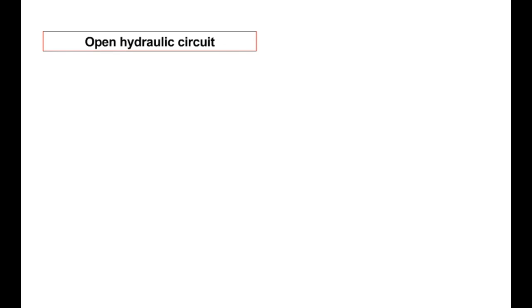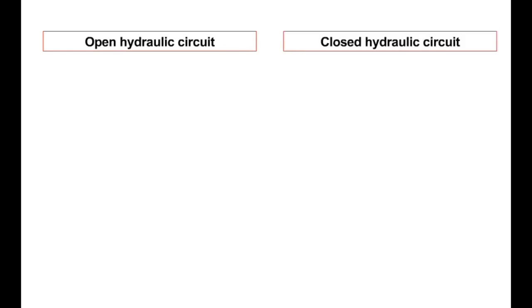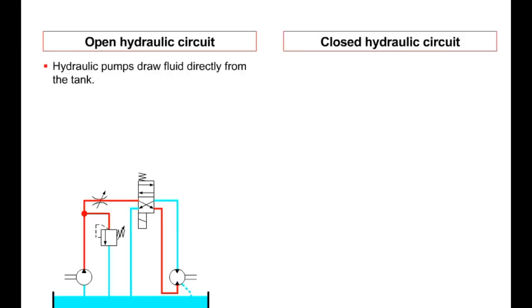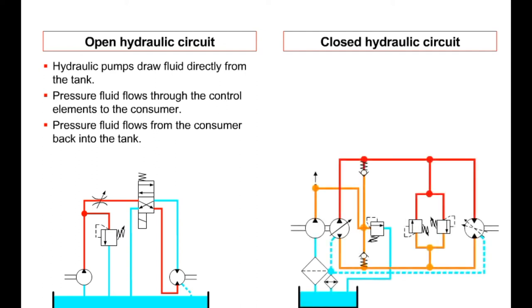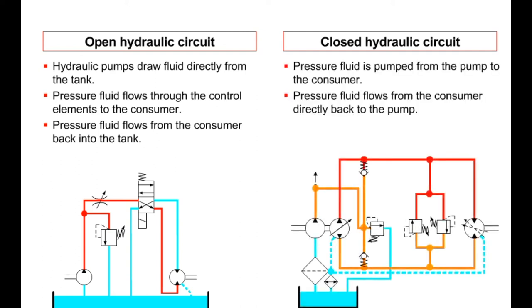We generally differentiate between two types of circuits: open hydraulic circuits and closed hydraulic circuits. In an open circuit, the hydraulic pump draws fluid from the tank and feeds it to the consumer via the control elements — in this example, the hydraulic motor is the consumer. The fluid then flows from the consumer back into the tank. We speak of a closed hydraulic circuit when the fluid flowing back from the consumer is fed directly back into the hydraulic pump.